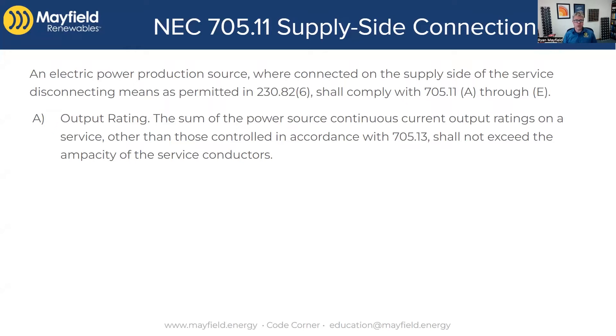What 705.11a is saying is that the sum of the power source continuous current output ratings on a service — other than those controlled by a power control system defined in 705.13, which we're not going to talk about right now — we're just talking about traditional PV inverters connected to the supply side of a main disconnect. The sum of those shall not exceed the ampacity of the service conductors. So if you have a PV system connected to a service, you can't exceed what those service conductors are rated for. Those conductors are rated for a certain amount, and that's what we have to stick to.